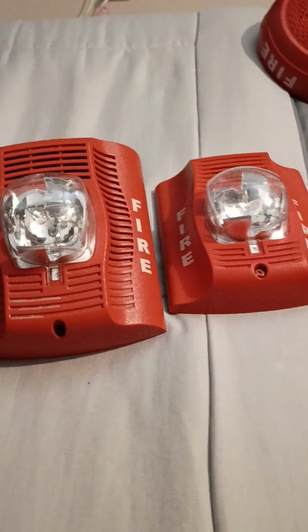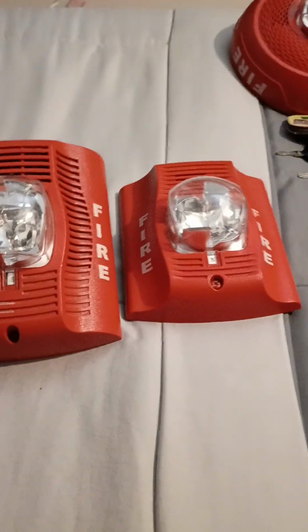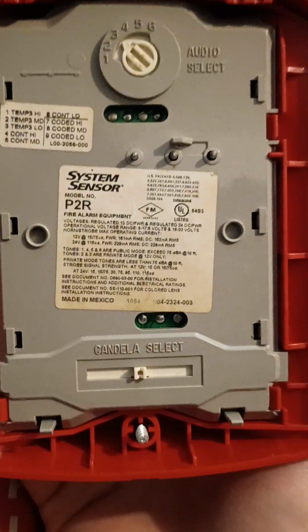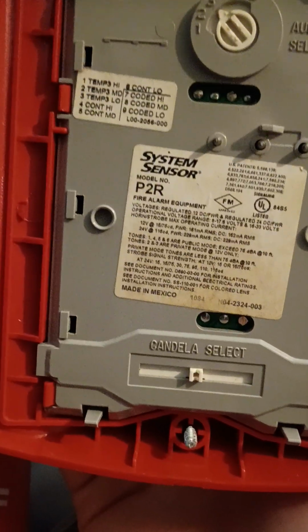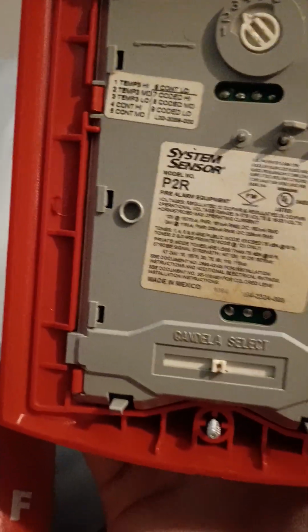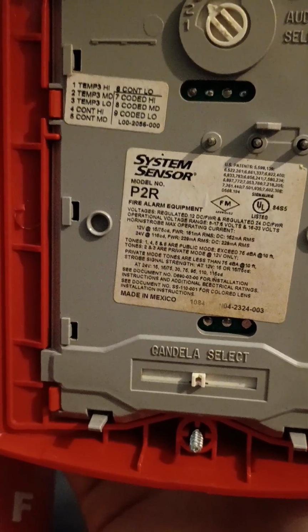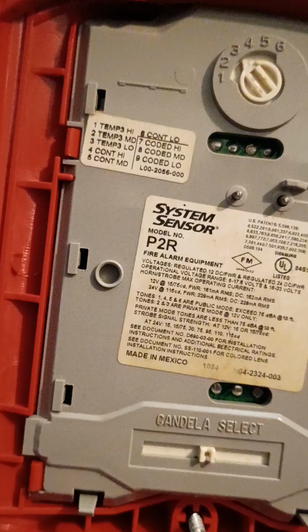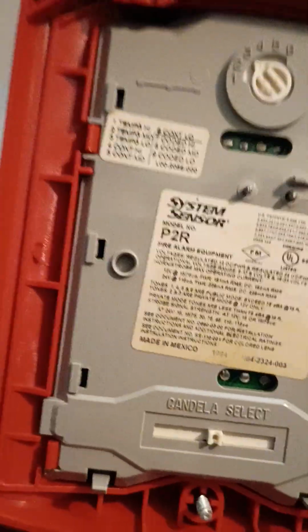Alright. Okay, so as you can tell, to the opposite side of that, we have my System Sensor P2R horn strobe. Alright. This device currently is on temporal code 3 low volume because it's on 3. So that is your audio selection. If you want continuous or temporal 3 or code 3, you would adjust this knob right here.